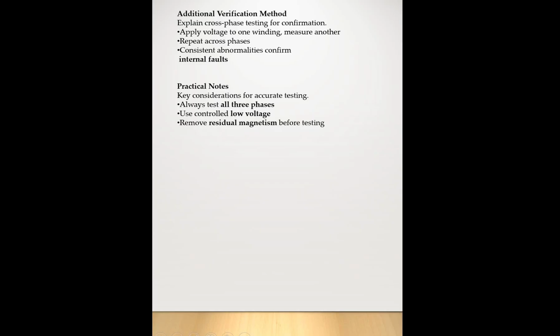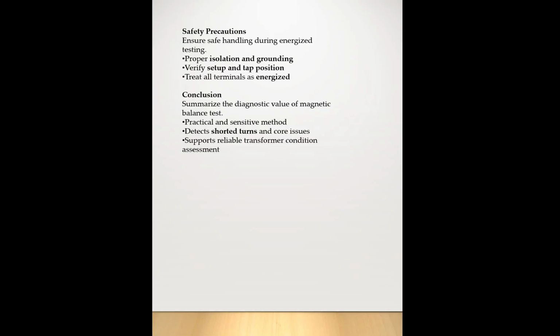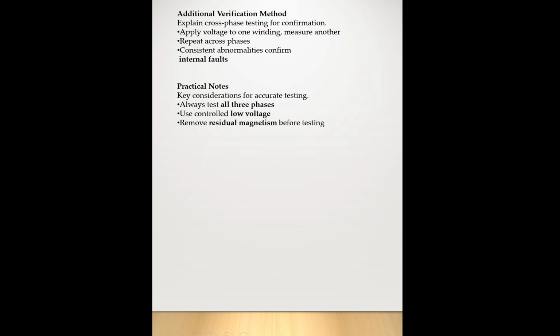Now, detection of shorted turns. So how does a fault manifest in the test result? A shorted turn forms low impedance loops, causes circulating currents, and the induced voltage drops significantly. Okay. And additional cross-phase testing confirms this: apply voltage to one winding and measure another, repeat across phases, and consistent abnormalities confirm internal faults. The key practical notice is key considerations for accurate testing.